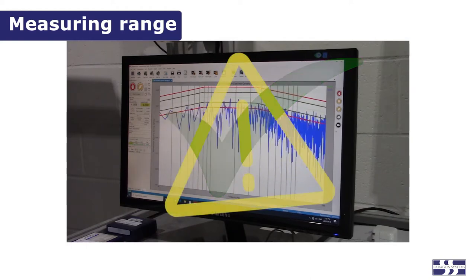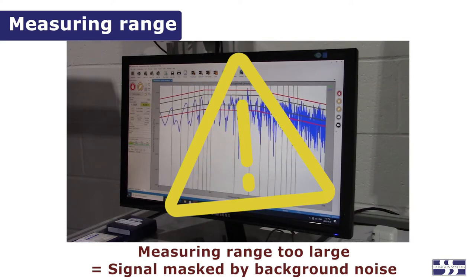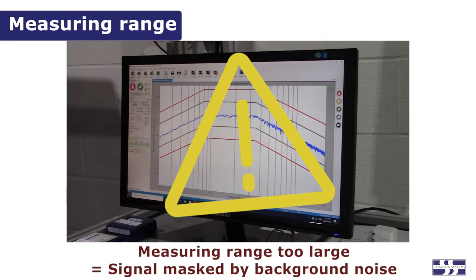However, using too large a measuring range can make it difficult for the vibration controller to see the accelerometer signal above the background electrical noise.